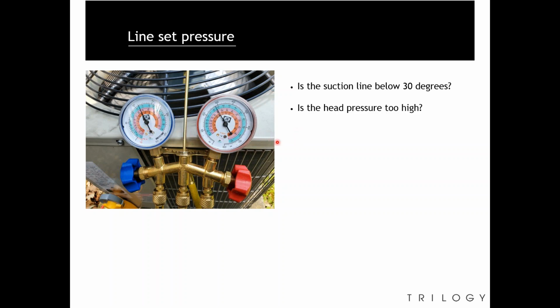Is the head pressure too high? So this is the high side pressure. If that's too high, we may have a dirty filter. The coils could be dirty. That's usually an indicator of high head pressure.